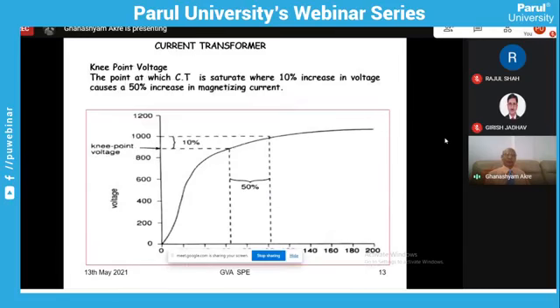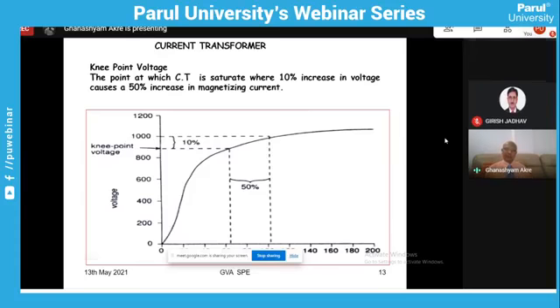What is the effect of the voltage developed across secondary due to VA, that is volt ampere burden? Here that voltage will produce flux density, and flux density will draw the excitation current, and that is how we can have the errors in the transformers. But in the general transformer principle, you see, in case of the current transformer of protection system, the high voltages are developed across the secondaries because the relay has to have the high voltages proportional to the fault current. Fault current may be 20 times. So it is the 20 times the voltage it will take.